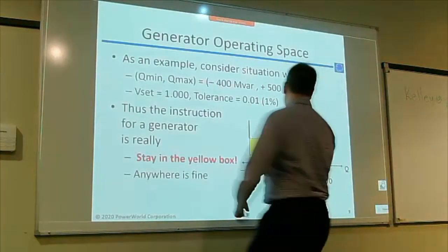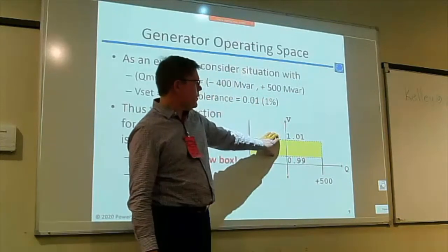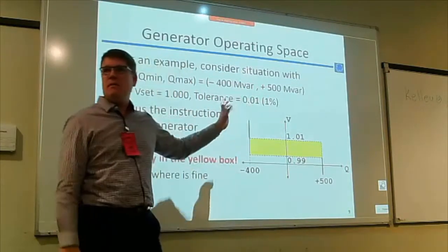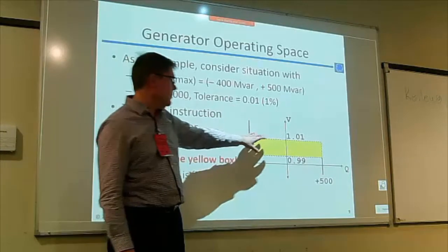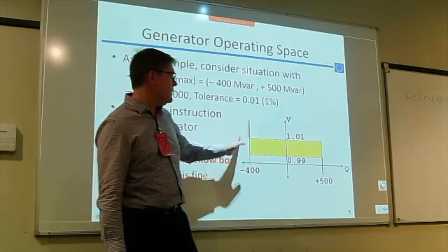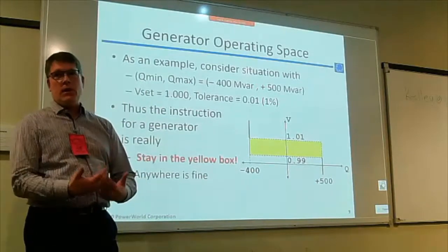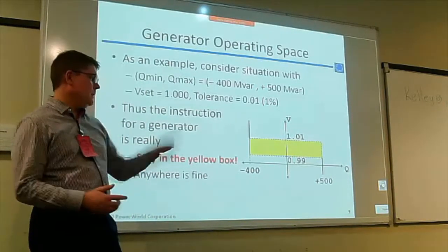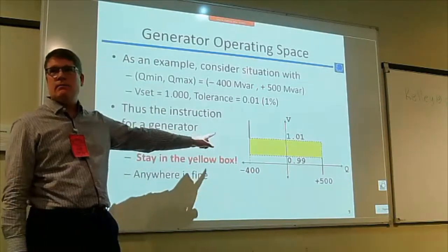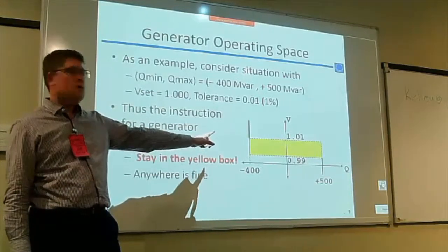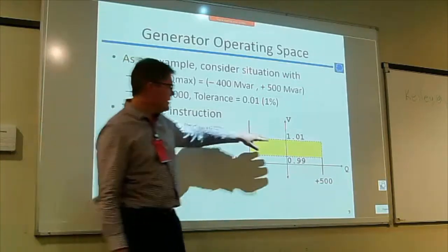That's a big voltage difference in our power flow world. So the fact is, and what I was hearing from them, 2% is not unusual. If you tell me to be at 1.04, I'm like, okay, somewhere between 1.02 and 1.06, I'm good. That might be a little wide, but that's what the generators actually do with the information given to them. So that is beneficial to consider.